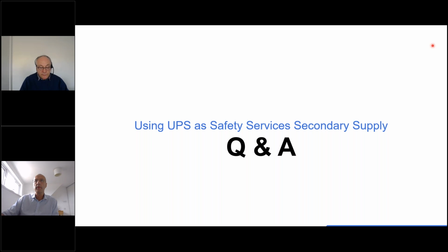Thank you. The next question is, does the UPS input and output cabling need to be fire rated? That depends where you're talking. If the UPS needs to be in a fire rated enclosure or room, rated for the required time, then the cables coming in and out of that room need to be fire rated. The cables inside the room won't.